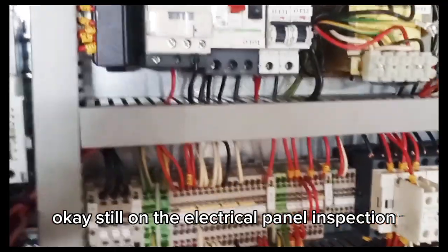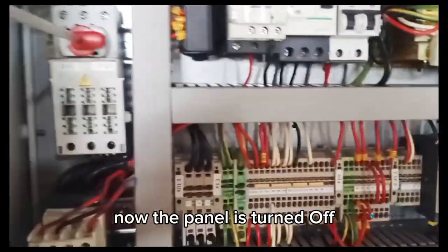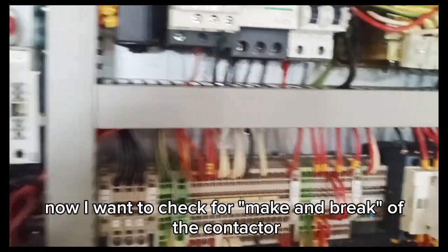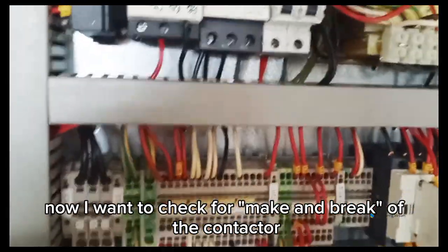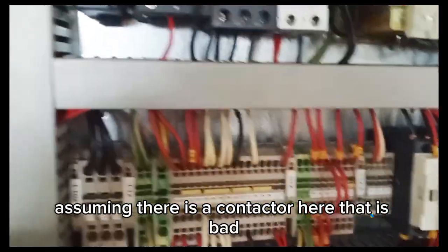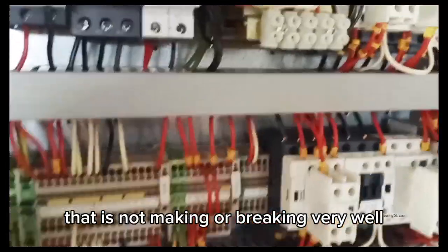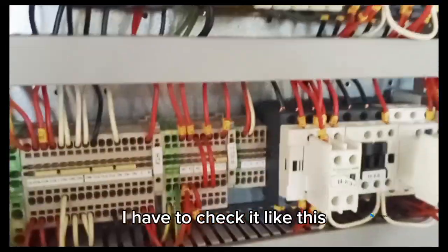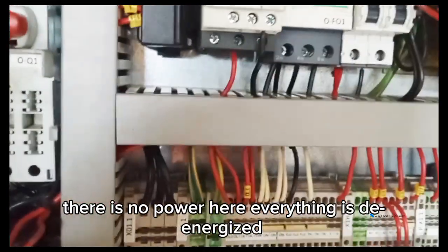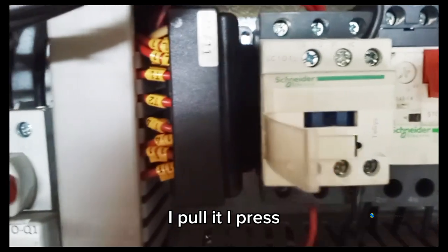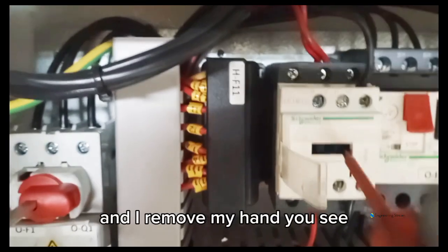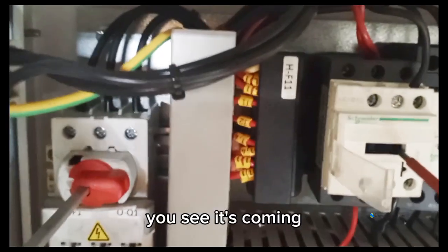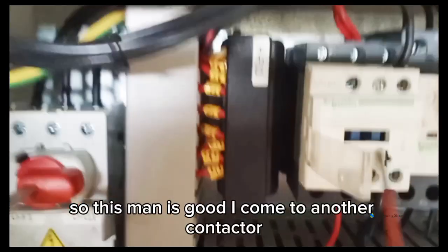Okay, still on the electrical panel inspection. Now the panel is turned off. I have isolated the panel. Now I want to check for make and break of the contactor. Assuming there is a contactor here that is bad, that is not making and breaking very well, I have to check it like this. There is no power here, everything is down. I come to this one, you see, I press, I depress, and I remove my hand. You see, it's making, and it's coming out. So this one is good.